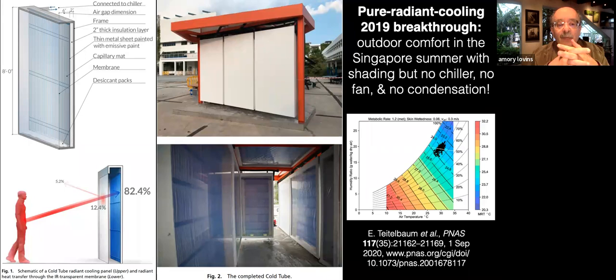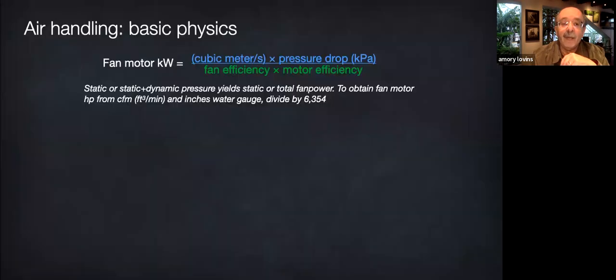Of course, radiative cooling, typically from ceilings or beams, is getting common in today's most efficient buildings. But previously, it had been thought to need tight control of indoor humidity to prevent condensation. Instead, this demonstration shows that you need only keep humid away from cool, and a few microns of plastic film can do that. Air handling in a radiatively cooled indoor space can then depend just on ventilation and health, not on cooling. That allows a lot less airflow, energy use, noise, and cost. More on this later.